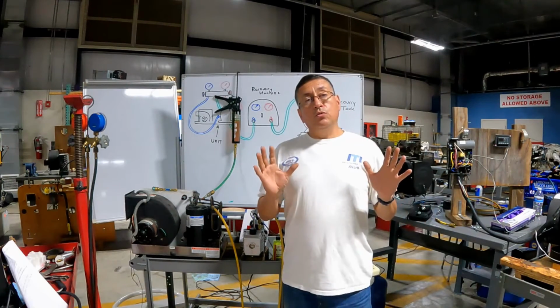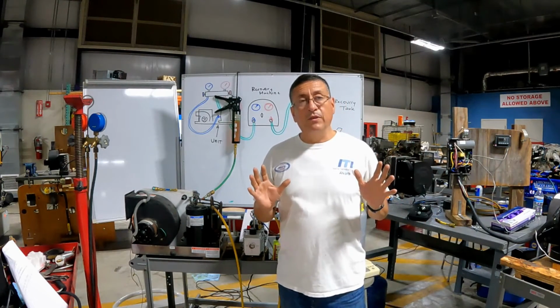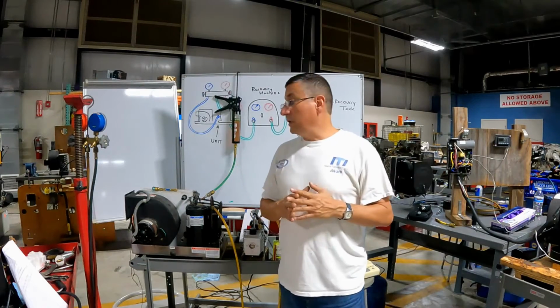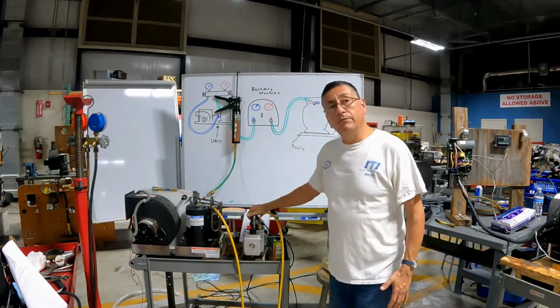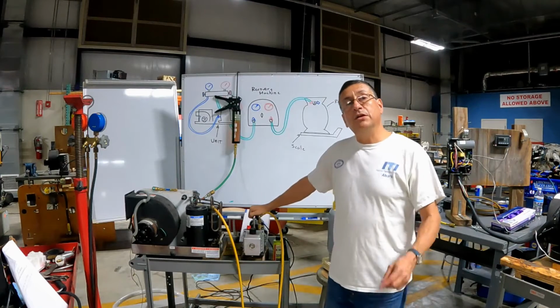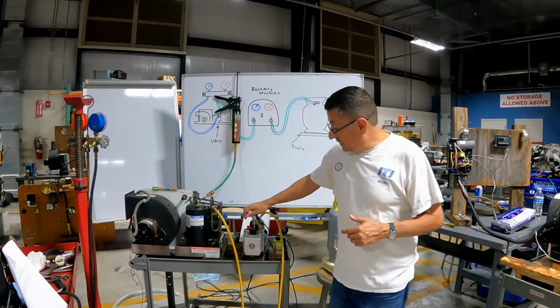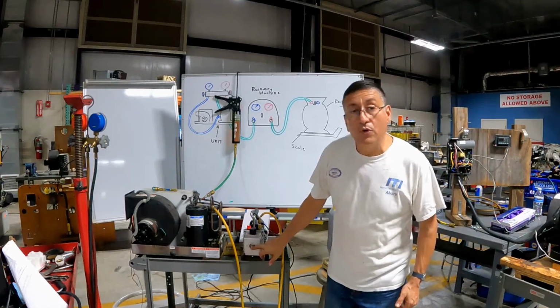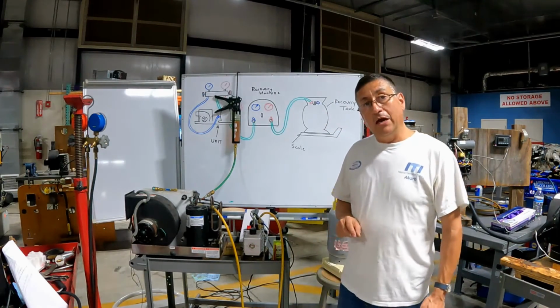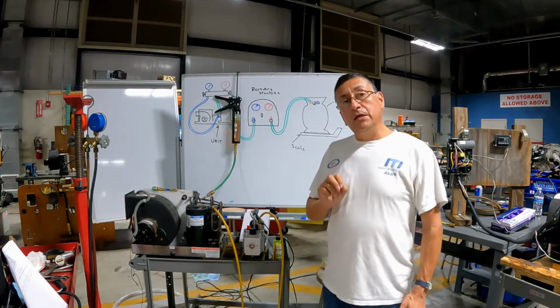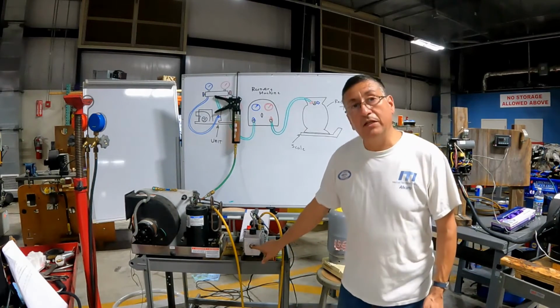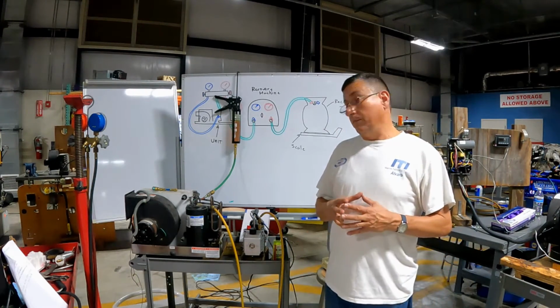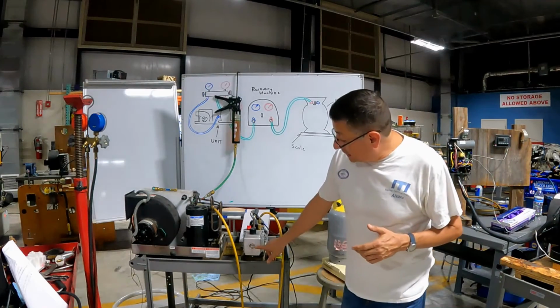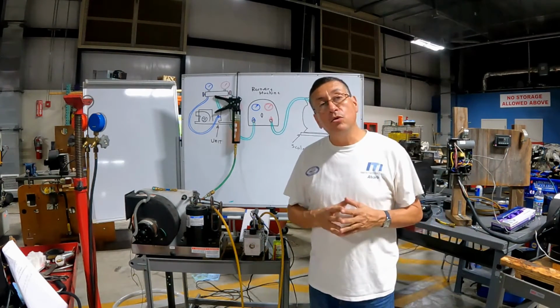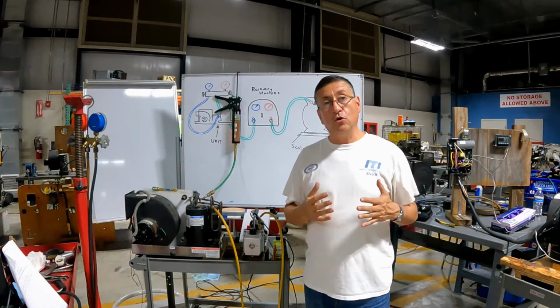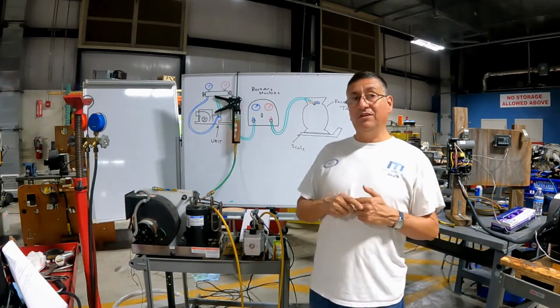Okay. Now we are going to do the process for the vacuum. In order to do the vacuum, we need the proper vacuum machine. This is the vacuum pump. It's a two-stage pump. The quality of the oil is important. The oil should be clear, transparent, and at the level recommended by the manufacturer. If you see that the oil is a little yellow, I recommend replacing it with fresh oil, the oil recommended for that specific pump.